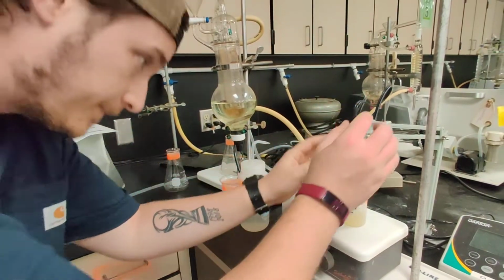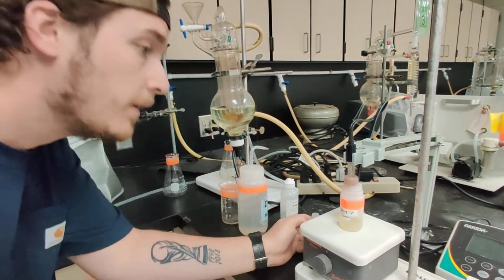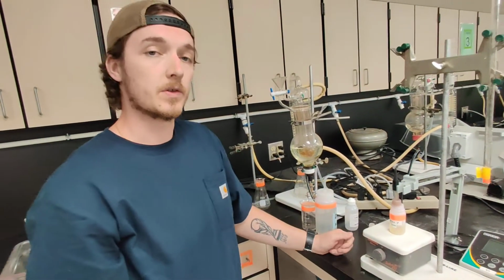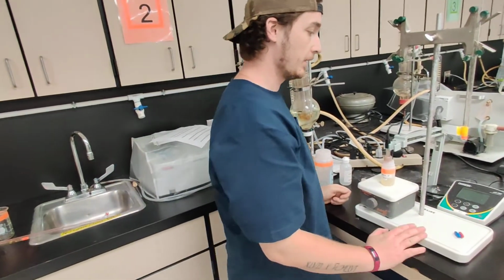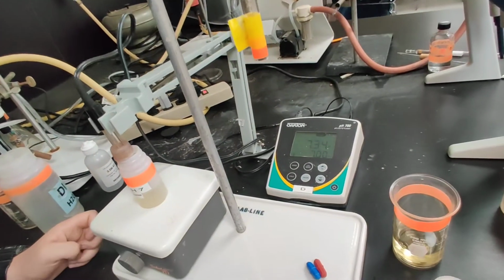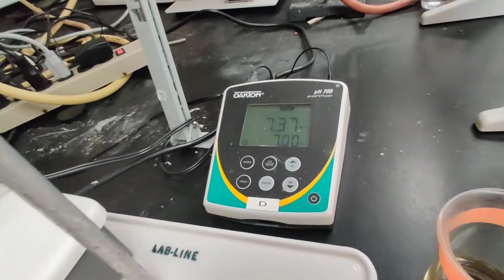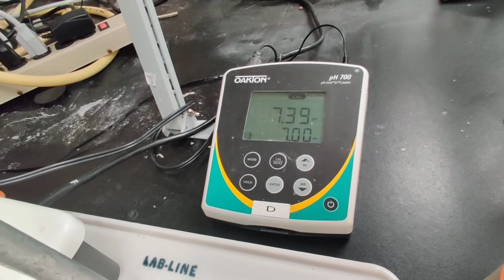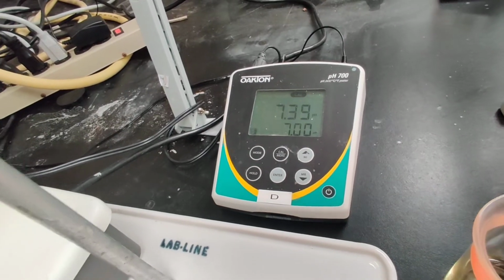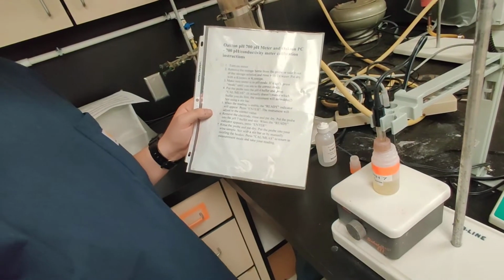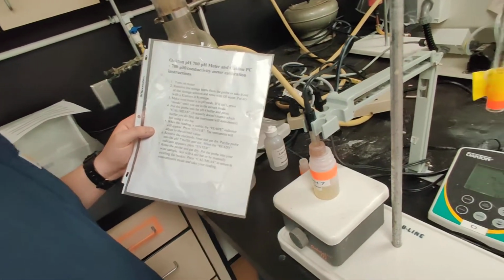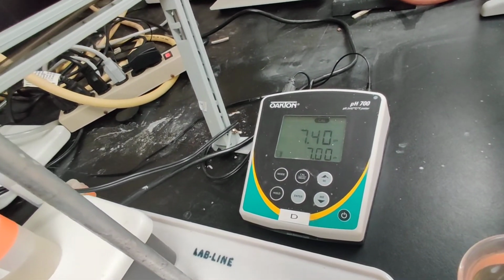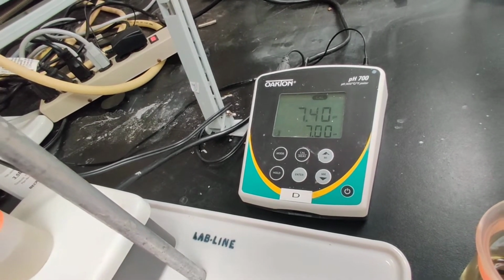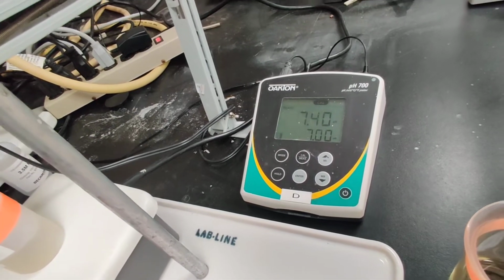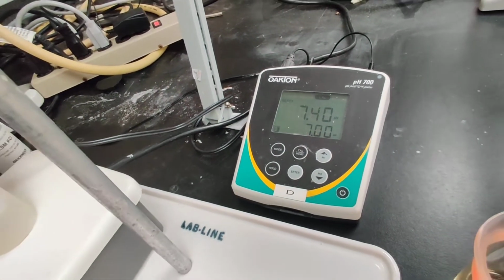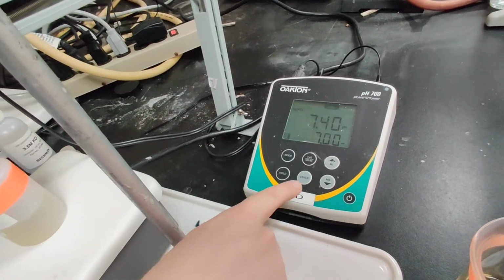Get the stirring going and get it open. Now you want to make sure the probe is not hitting the stir bar so as not to damage it. This will just work by itself until it says ready, and then we'll move on. Note that every pH meter should come with instructions. In this case, we have a list of instructions to follow, and you always want to follow these instructions. It says ready, so we're good to move on. It says ready, we'll hit enter.